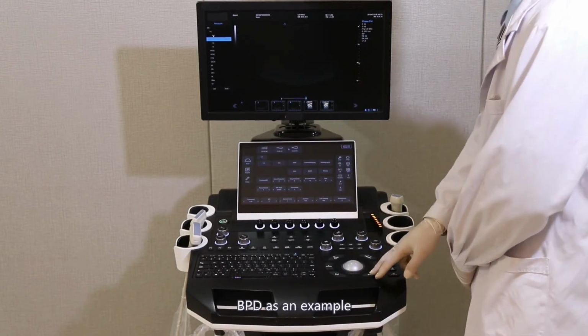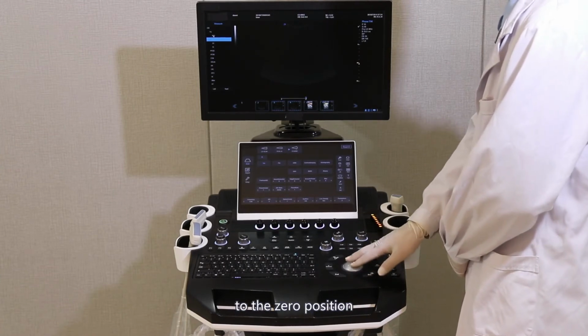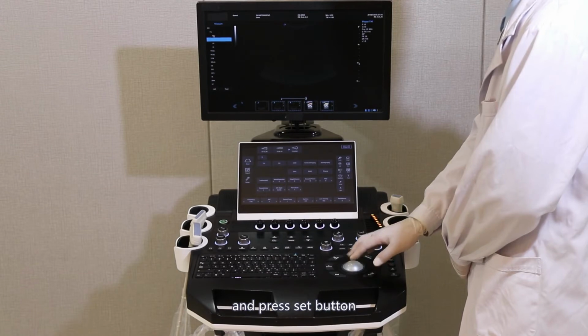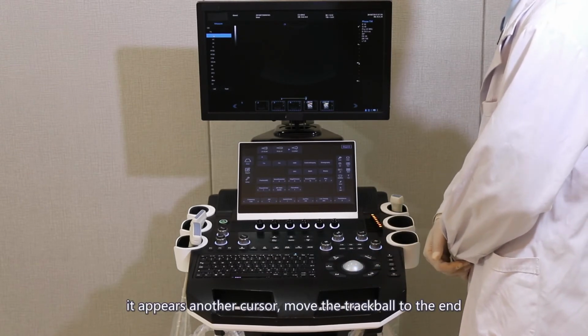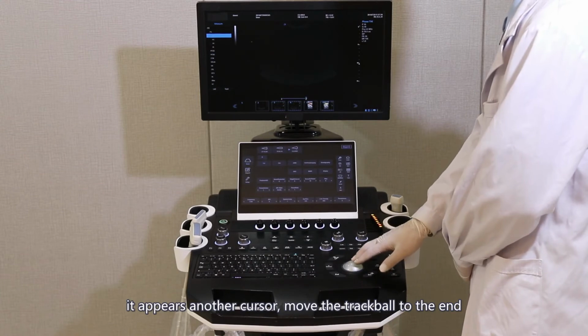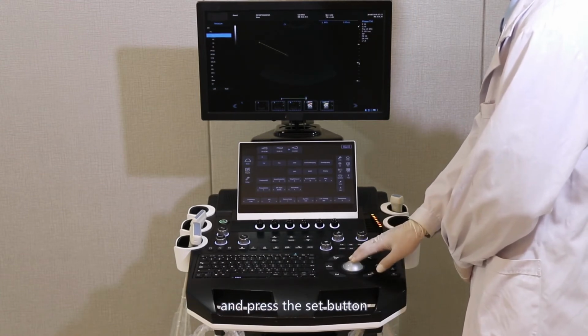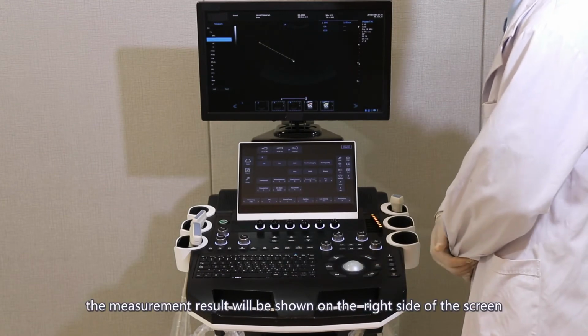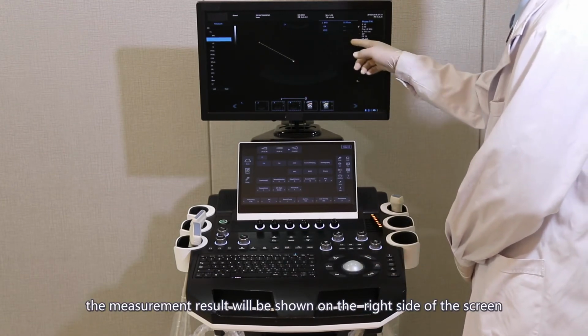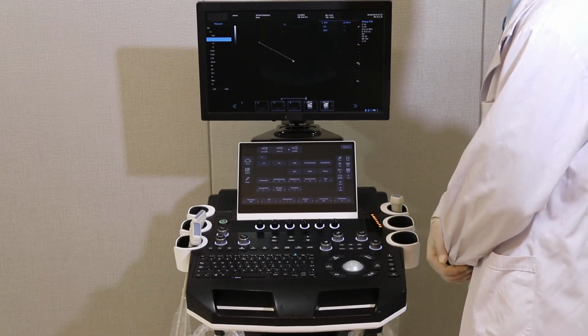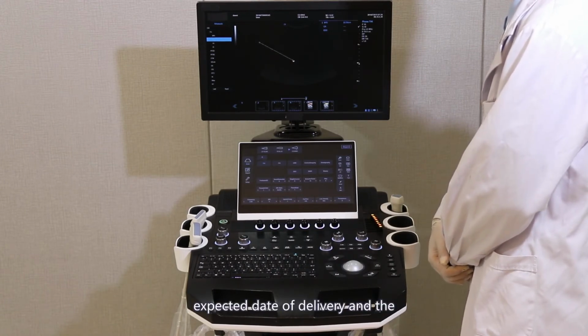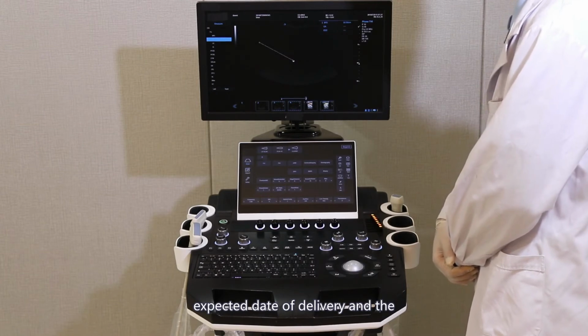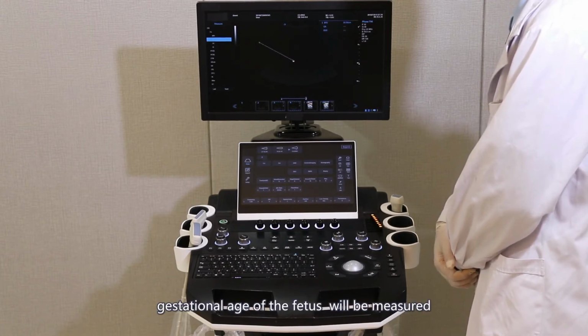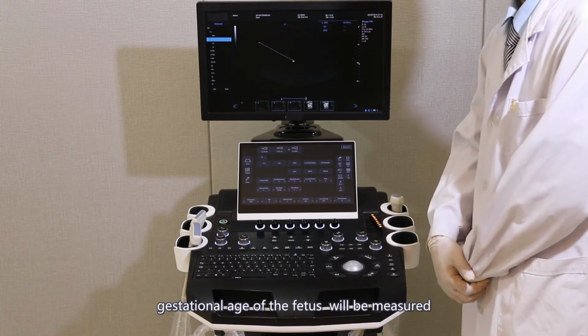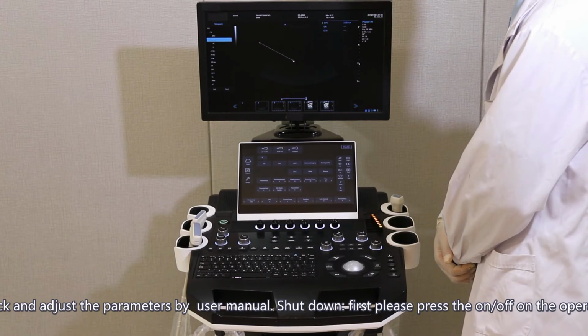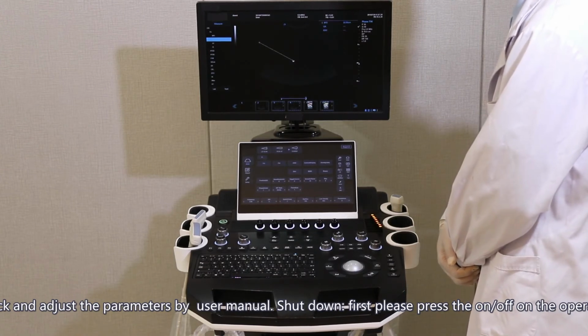Take BPD as an example. Move the cursor to the 0 position and press the Set button. Another cursor appears. Move the trackball to the end and press the Set button. The measurement result will be shown on the right side of the screen. The expected date of delivery and the gestation age of the fetus will be measured. Please check and adjust the parameters by user manual.